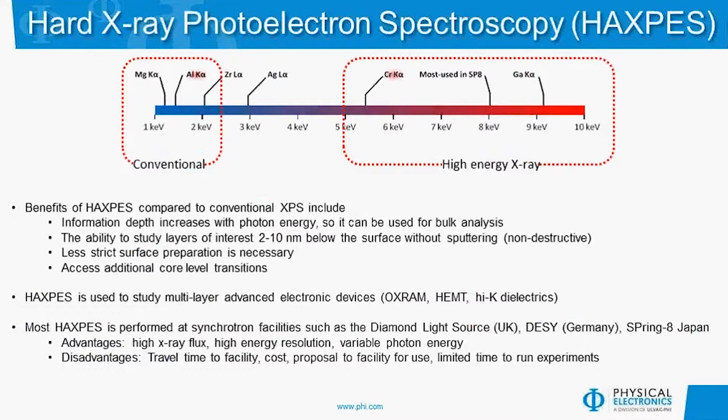HAXPES can be used to study layers of interest that are 2 to 10 nanometers below the surface without sputtering, making it non-destructive. Since HAXPES is not as surface sensitive as XPS, there are less strict requirements for preparing a sample surface. In addition, higher photon energies mean that higher energy core electrons can be accessed. Currently, HAXPES is used to study multi-layer advanced electronic devices such as Oxram, HEMT, or Hi-K dielectrics.